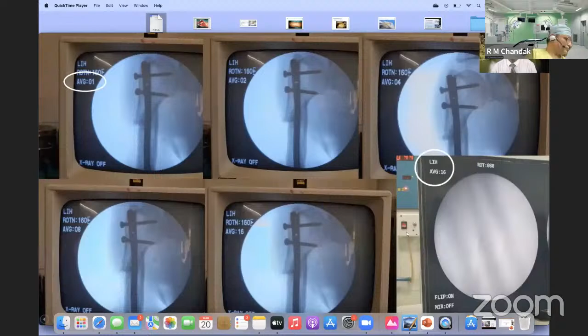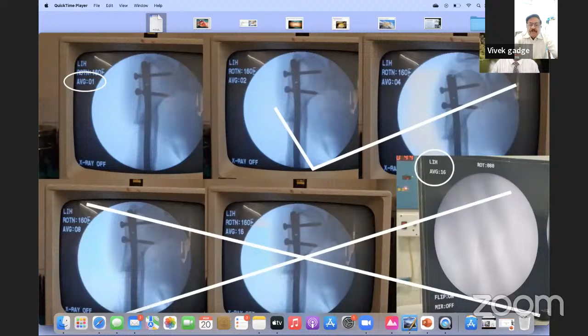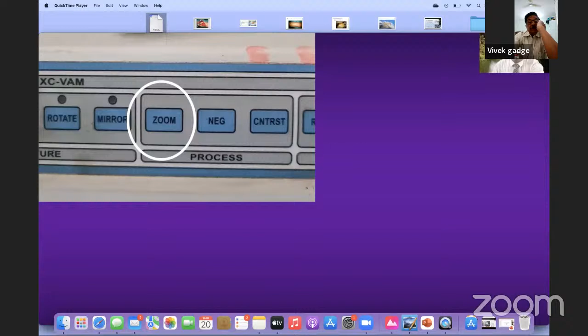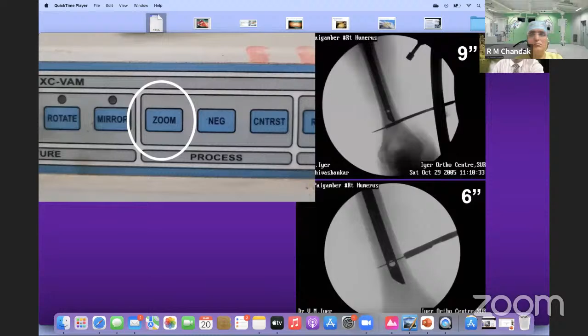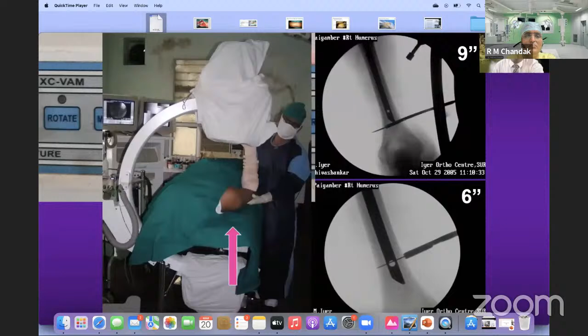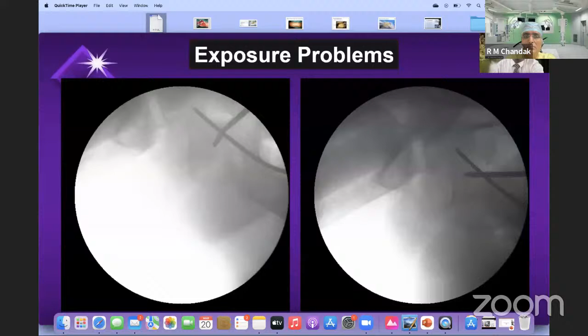Regularly, we orthopedic surgeons, to get good quality picture, keep it at average of 16. That is an unnecessary radiation we are taking. So keep the average as low as possible. I normally keep it at either 2 or 4, and only rarely I go above. And you should not use unnecessary 16 or 32 radiation. Zoom also, when you zoom through the memory unit, it unnecessarily requires more radiation, KV increases. So instead of that, what you can do is you can take the X-ray unit up near to the body, and that will give a large zooming automatically with the same amount of radiation.